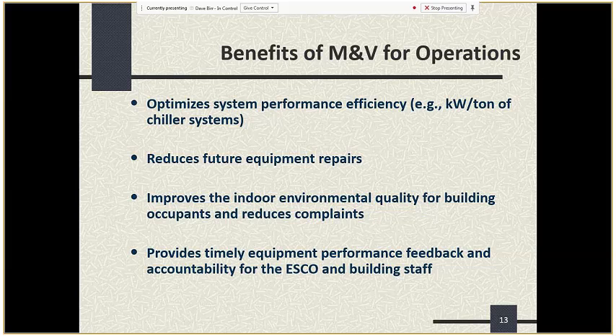The existing chiller baseline kW was about 1.1 kW per ton, and it's being reduced to 0.773 kW per ton currently, and probably it's going to improve over that as we fully implement the optimization strategies as the OST pipeline work is finished. But even the initial reduction from 1.1 kW per ton to 0.773 kW per ton is like a 30% reduction, which is very substantial.